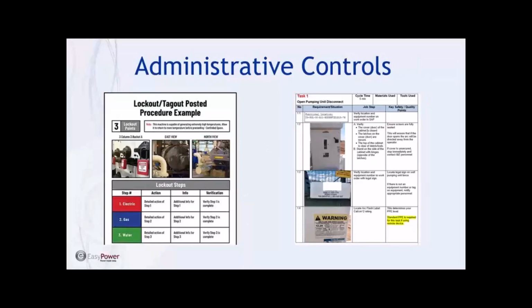I always give two examples of administrative controls in terms of procedures, and the first is just a lockout/tagout posting. The idea is that with a lockout/tagout posting, I could come to your facility, having never been there before, and lock out and tag out a piece of equipment I've never worked on, and do it effectively, because all I really have to do is look at that posting or procedure telling me exactly what to do in terms of isolating the electricity, gas, or water. It's visual, there are pictures, and it's a step-by-step process that walks me right through it.